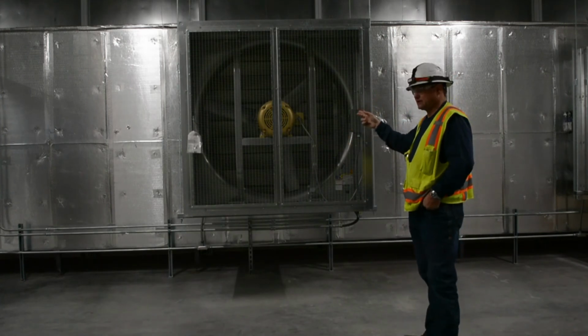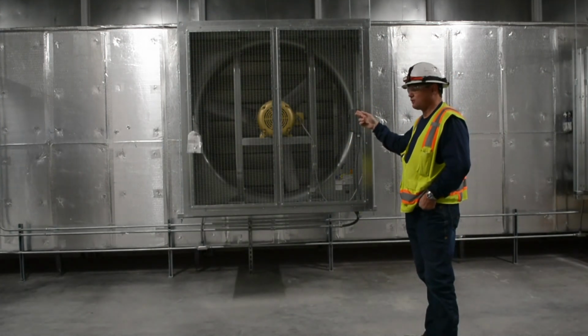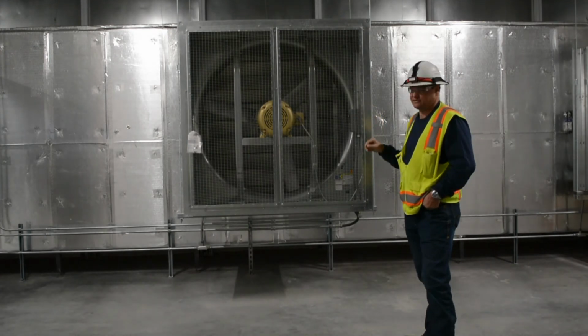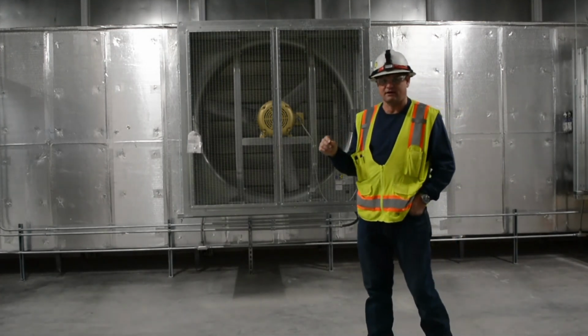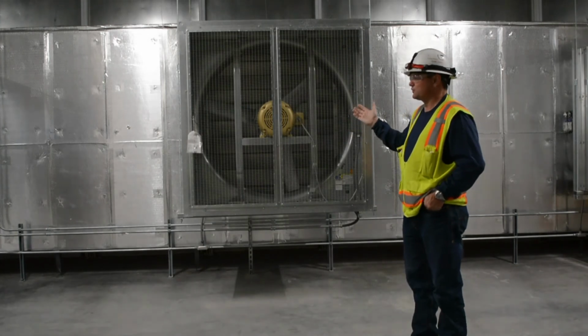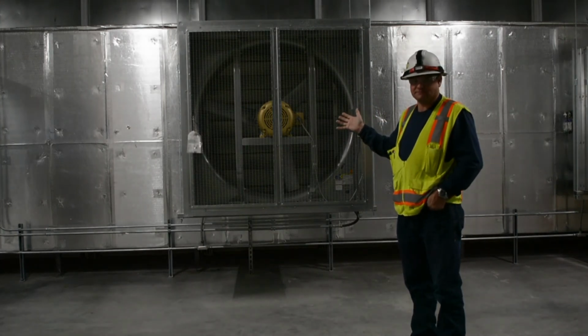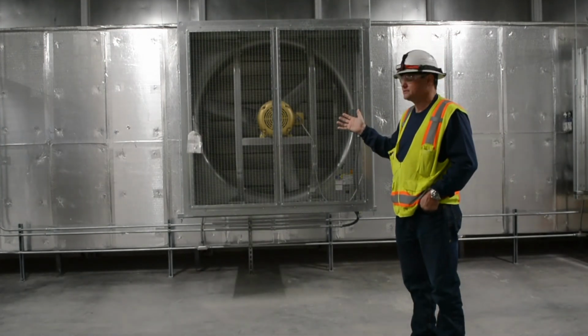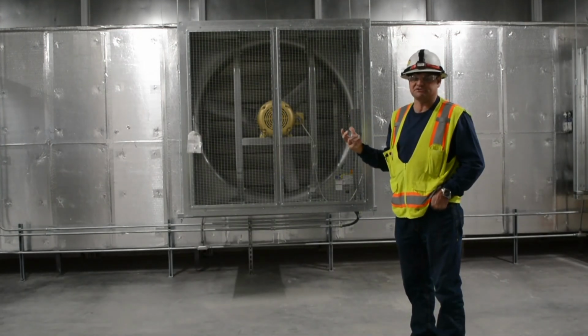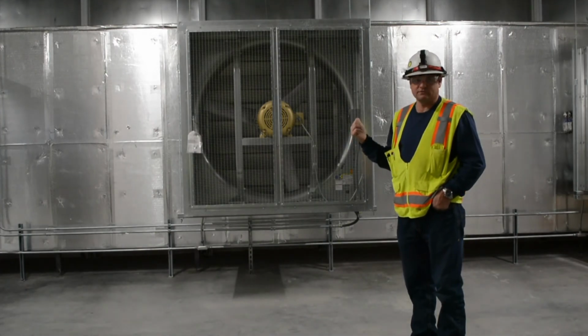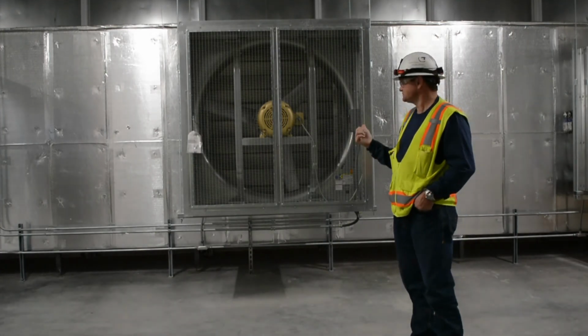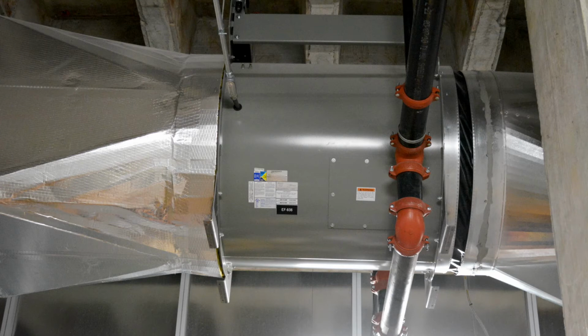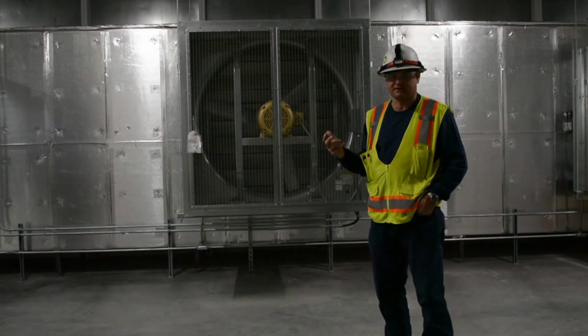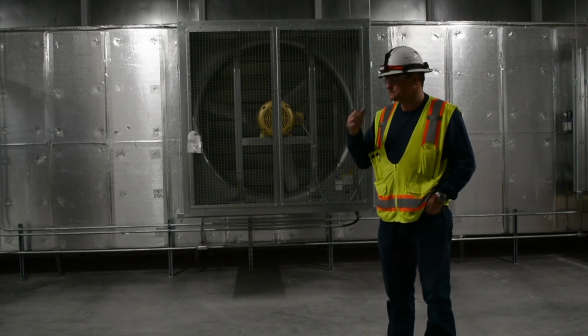You've got Baldor Super E motors, which is standard spec on all of the fans for this facility. They too also need lubrication every 8,000 run hours. So these fans in particular will not obviously run all the time. So most of the time in the summer they'll be off. But wintertime, yes, they will probably be on. So you'll have to calculate how many run hours you think have occurred in order to maintain the proper lubrication intervals. Other fans in the facility do run full time. So you'll need to ensure that you're getting to those quarterly and inspecting the lubrication requirements.